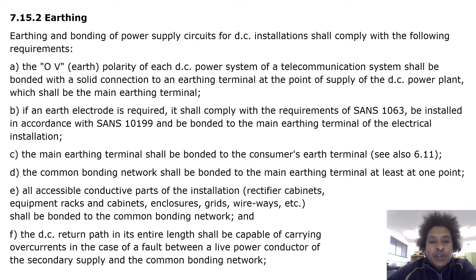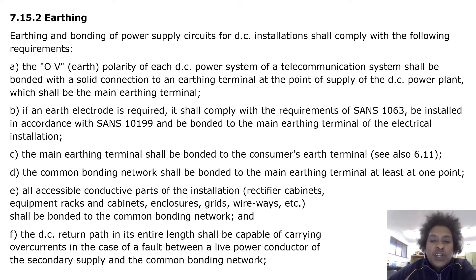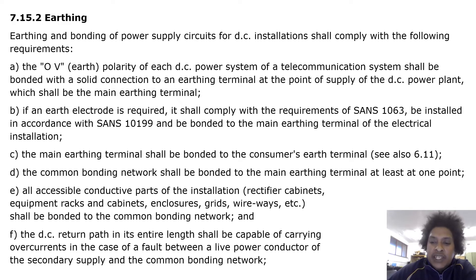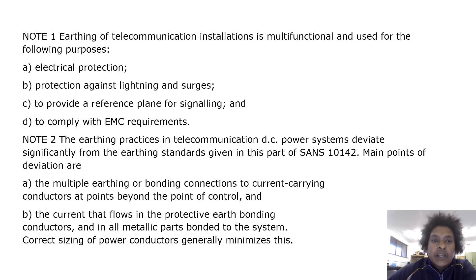All accessible conductive parts of the installation — rectifier cabinets, equipment racks and cabinets, enclosures, grids, wireways, etc. — shall be bonded to the common bonding network. The DC return path in its entire length shall be capable of carrying overcurrents in the case of a fault between a live power conductor of the secondary supply and the common bonding network.